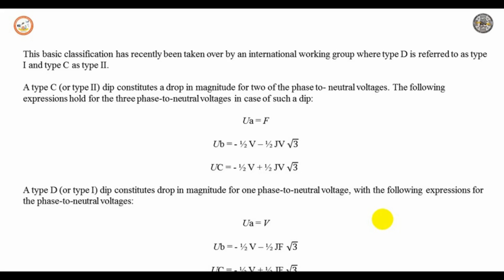At transmission and sub-transmission level, the PN factor is very close to the pre-fault positive sequence voltage for a dip due to a single phase or phase-to-phase fault. Whenever it is close to load, the PN factor becomes smaller, especially due to the impact of induction motor load. Here we assume the PN factor to be equal to the pre-fault voltage at the PCC, and we will calculate the impact of distributed generation on both the characteristic voltage and the PN factor.